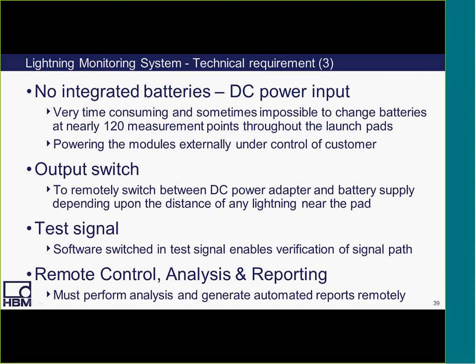And finally, no integrated batteries. It needed to have a DC power input. It is very time-consuming and sometimes impossible to change batteries at nearly, let's say, 120 measurement points throughout the launch pad. So powering the modules externally under control of the customer had to be provided. Also, an output switch to remotely switch between DC power adapter and a battery supply, depending upon the distance of any lightning near the pad, had to be provided. A test signal, so that via software you could switch in a test signal to do a verification of the signal path for each of the channels. And then remote control, analysis and reporting was important, so that analysis and reports could be generated automatically for every triggered condition.